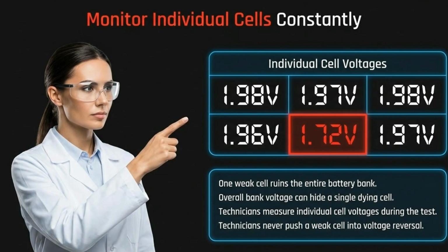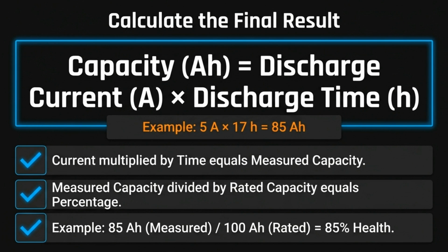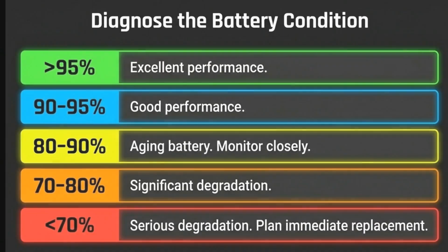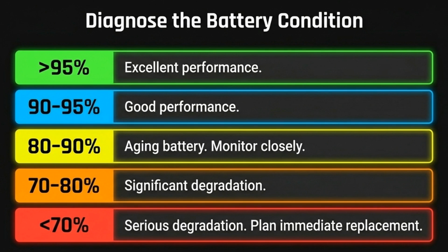A single weak cell can ruin an entire battery bank, so never push a cell into voltage reversal. Calculate your final result by multiplying the discharge current by the total time. Divide this measured capacity by the rated capacity to determine the battery's health percentage. Use these metrics to diagnose the battery. Anything above 95% is excellent, while capacity below 70% indicates serious degradation that requires immediate replacement.